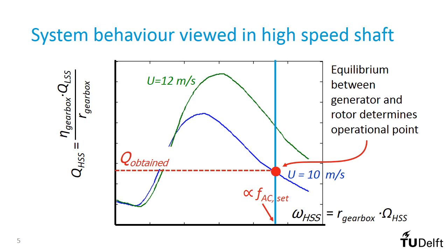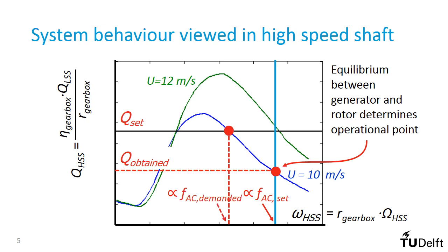For different wind speeds, it would intersect at different heights with the relevant rotor curve. However, with the back-to-back converter, the generator can also be controlled differently. It is also possible to set the torque in the generator and adjust the electrical frequency according to the demand. In this case, the operational point is found at the intersection with the horizontal line, and the demanded electrical frequency follows from the resulting rotational speed. This analysis shows that it is not the wind or the rotor aerodynamics that determine the speed of the rotor. They do play a crucial role through the CQ-lambda curve, but it is the control of the generator that is decisive.